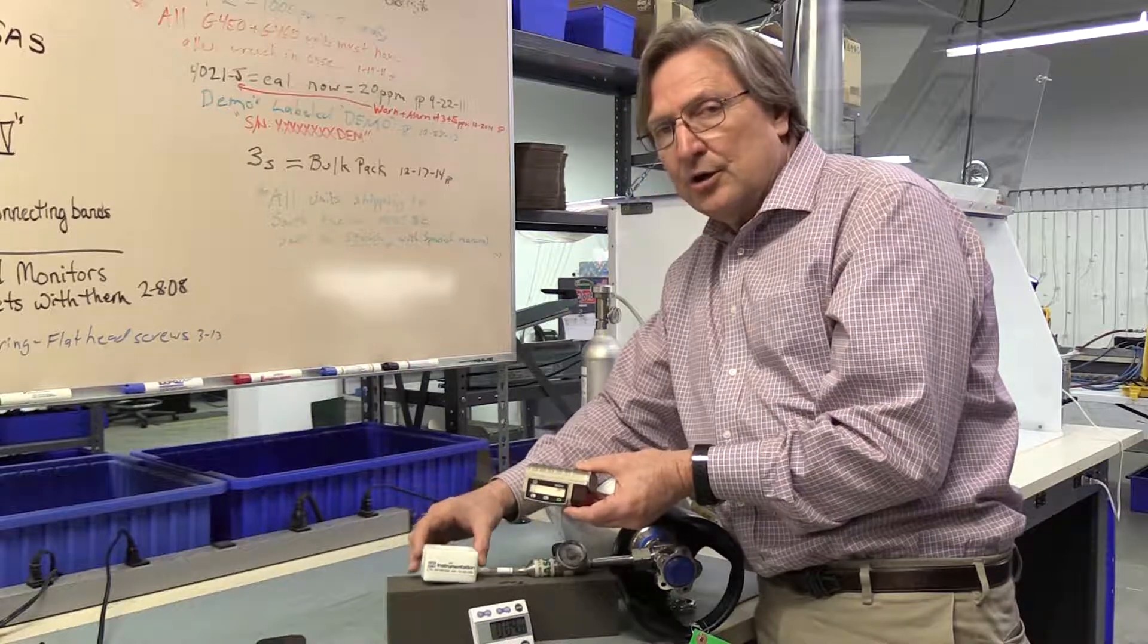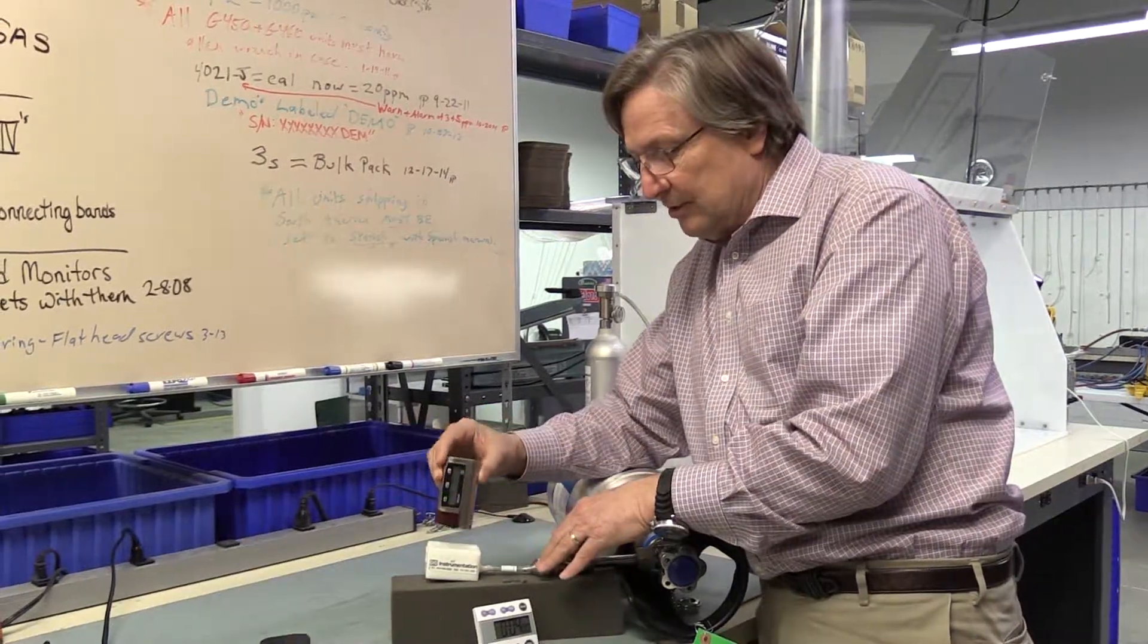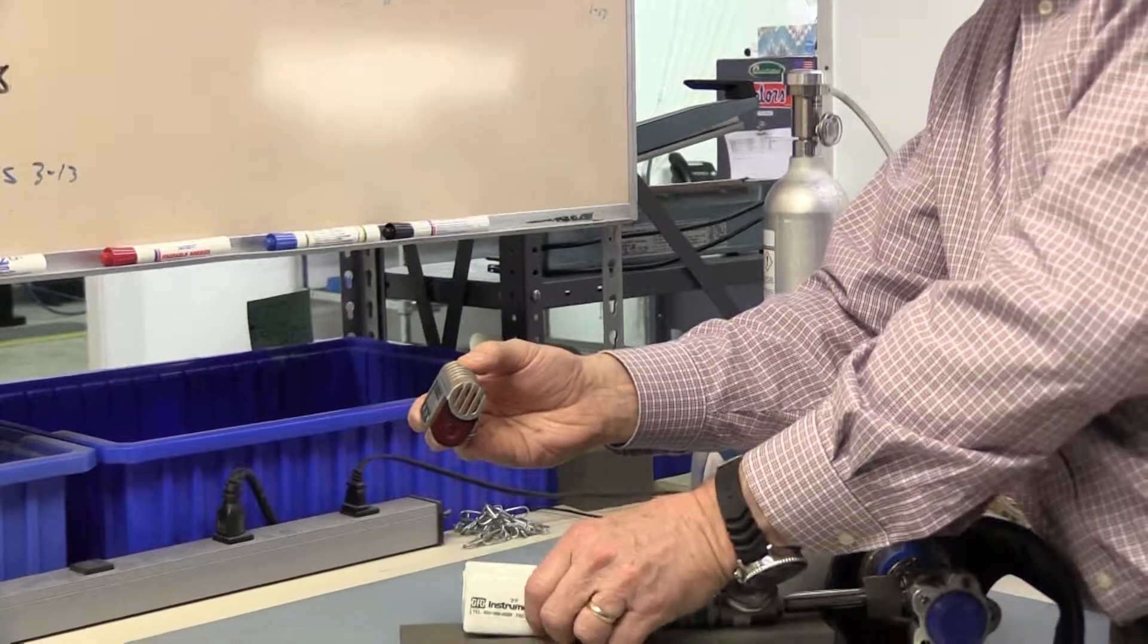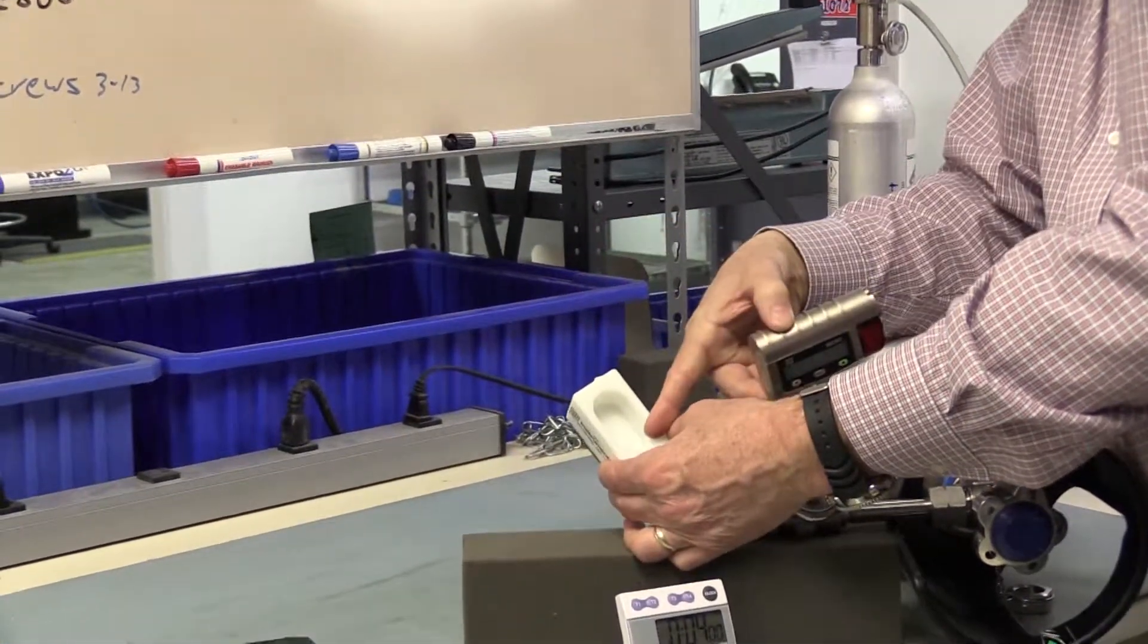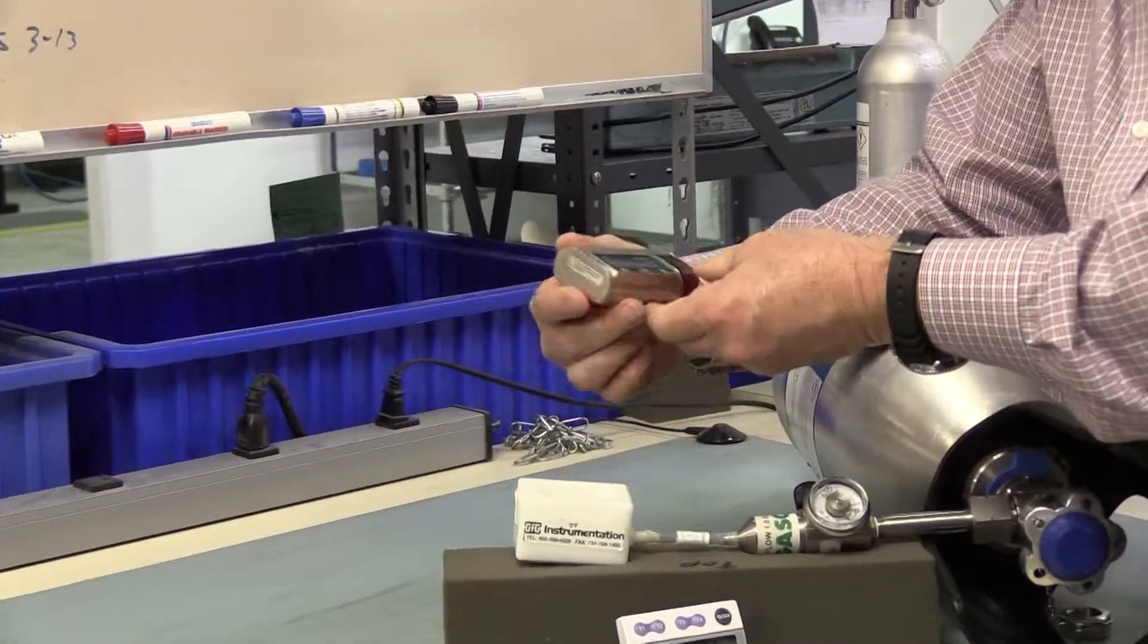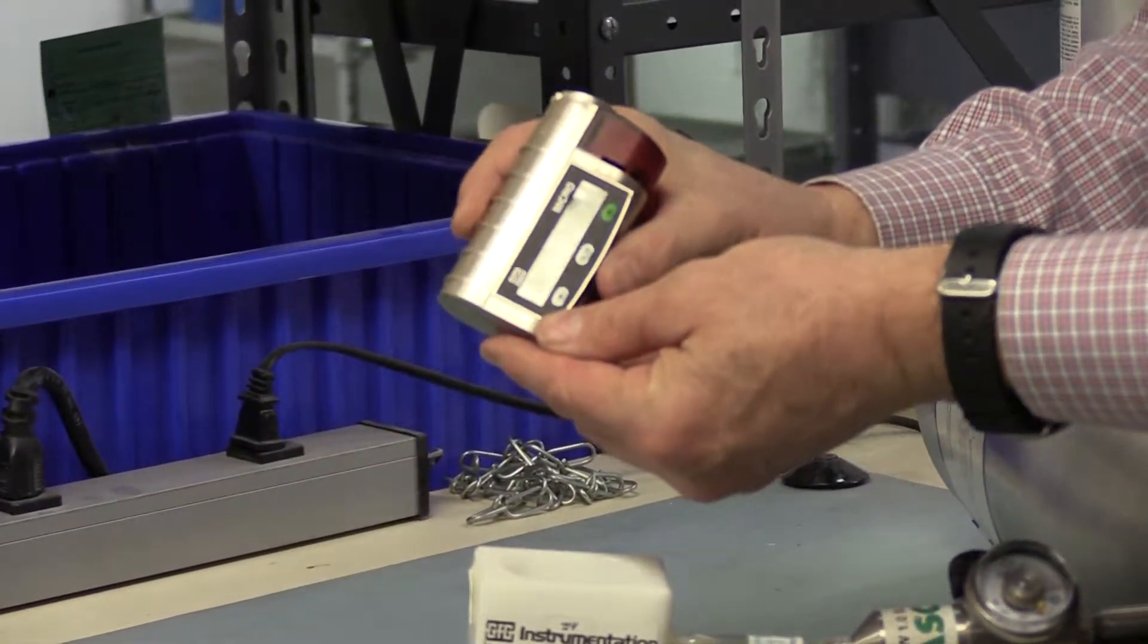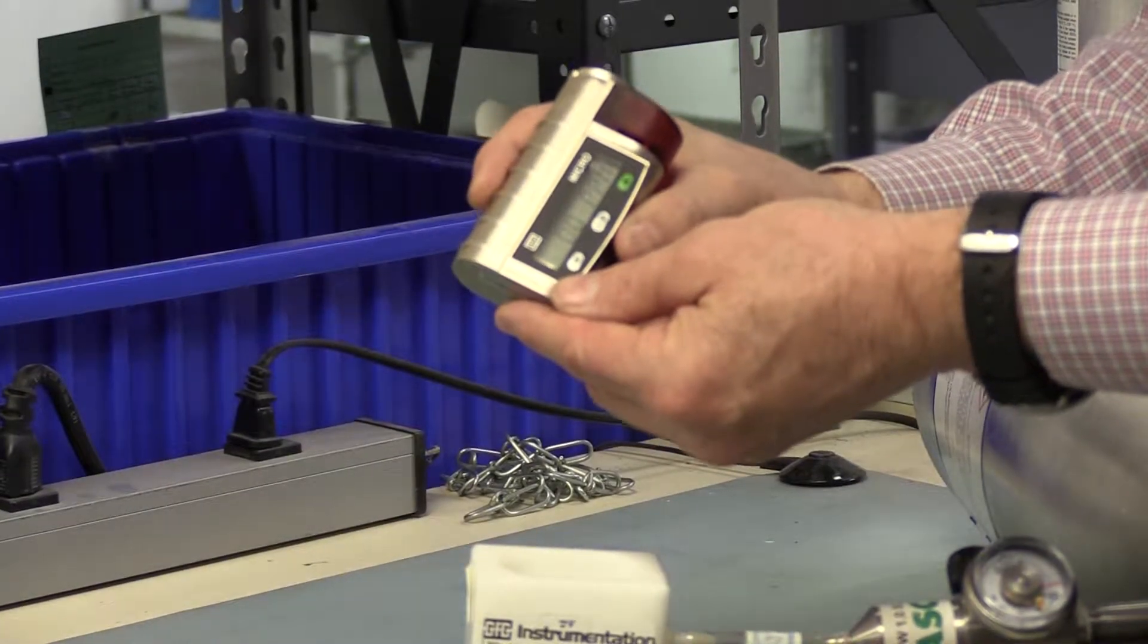The calibration adapter is made of Teflon. Make sure when we put the instrument into the adapter, that the side of the instrument where the sensor is located is lined up with the side of the Teflon adapter where the gas actually comes in. So what we're going to do is start out by making sure that the readings of the sensor in fresh air really are 0.0 parts per million.